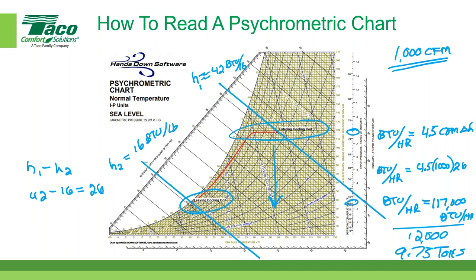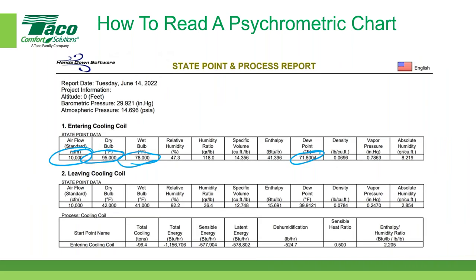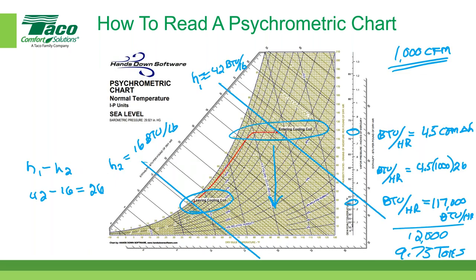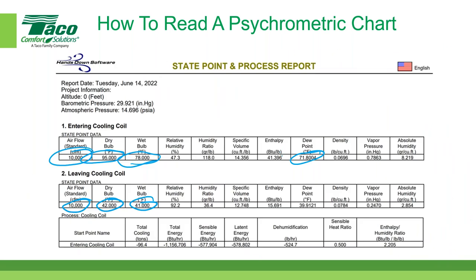Now remember, the chart is gross, but the calculation is much more accurate. And then the final condition, again 10,000 CFM, 42 degree dry bulb, 41 degrees wet bulb. Here is my enthalpy. We said on our chart about 42; the actual is 41.396. And then the enthalpy at the discharge, I think we said was 16.